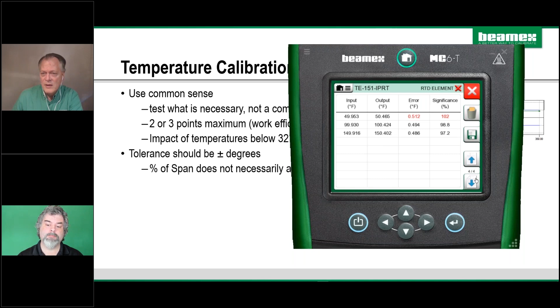And Roy, what does this mean? Does this mean you were bad? It failed? Yeah, that means I need remedial technician training if it fails. So no. I know this is one of your pet peeves. Yeah, it is. So I have this thing where nobody wants to be associated with a failed test. And if there's a failure, they'll cancel out of the test, they'll readjust it, make the tolerance larger, whatever. But the failure is the device under test. That's it.